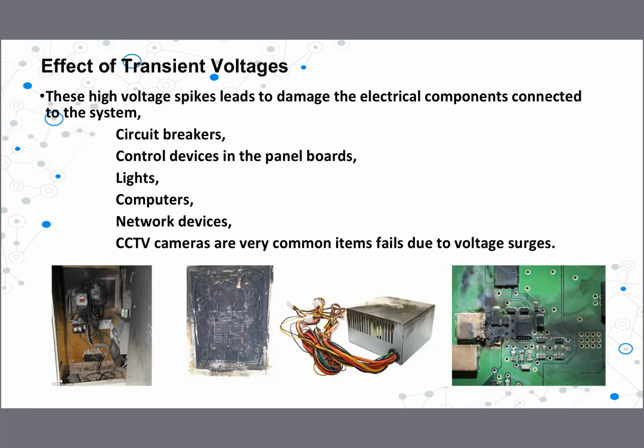Now here you can see in these images what I have shown here. The electrical power receiving point, meters, and circuit breakers are completely damaged due to this transient voltage. As I told you, there are various reasons for transient voltages. Let's look at what the reasons are. Certain reasons for transient voltages are highly dangerous. Now you can see here in the second image, the electrical panel is completely burned out.